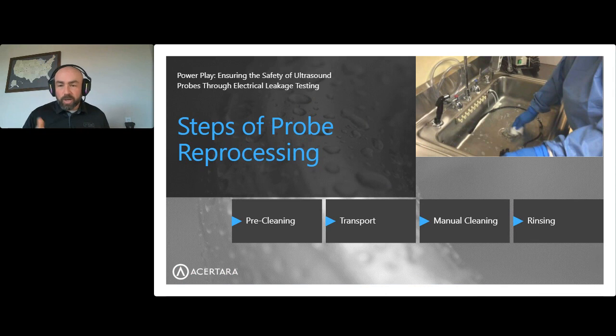So we were kind of talking back and forth with Lisa earlier, the steps of probe reprocessing start with the pre-cleaning. Once that pre-cleaning is done, the probe is transported typically to your facility's central processing or sterile processing. And you probably have a sink exactly like this one where you're actually doing the manual cleaning to make sure that all the patient material is off of the probe. Once this step is done, then you want to do your electric leakage testing. So you do your rinsing, you make sure everything is ready to go, and then you're ready to do that ELT to make sure that the probe doesn't have hidden damage.